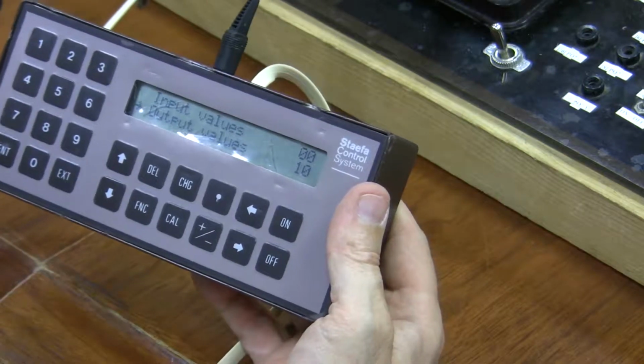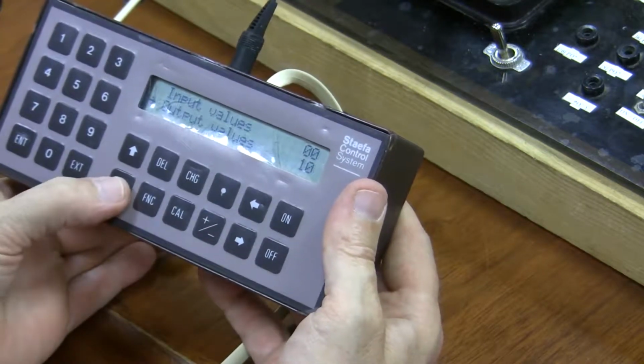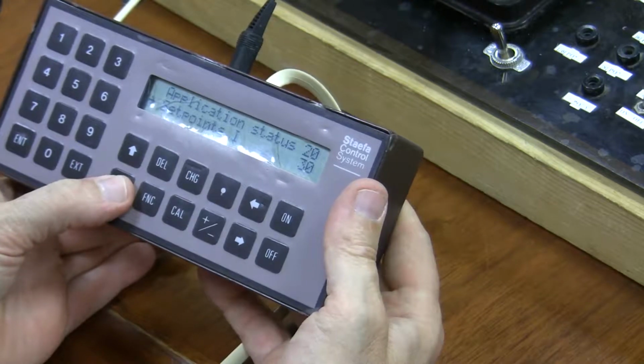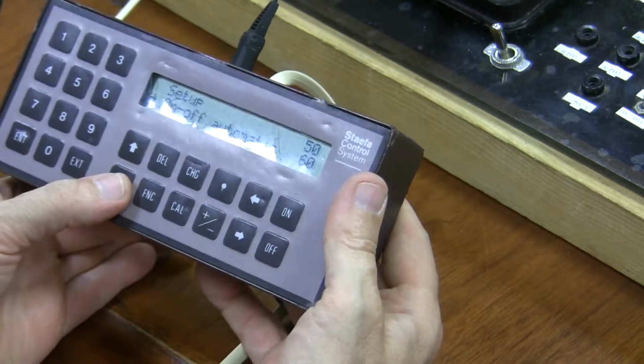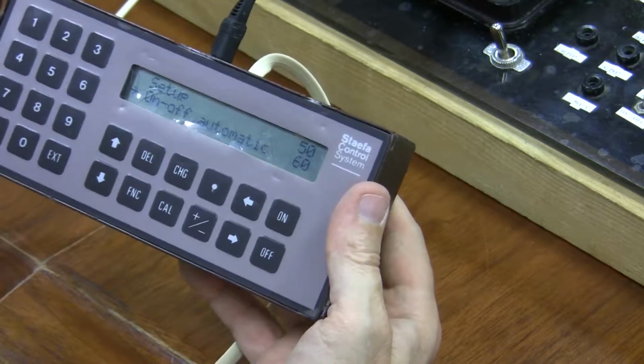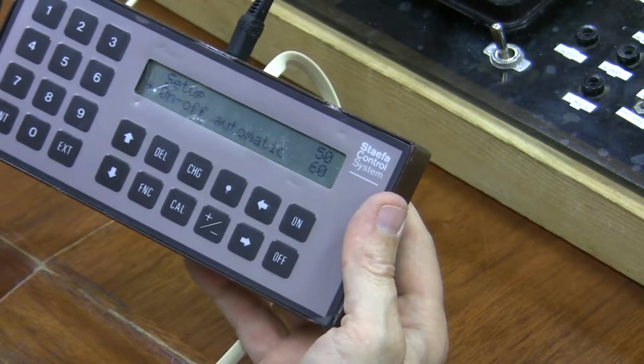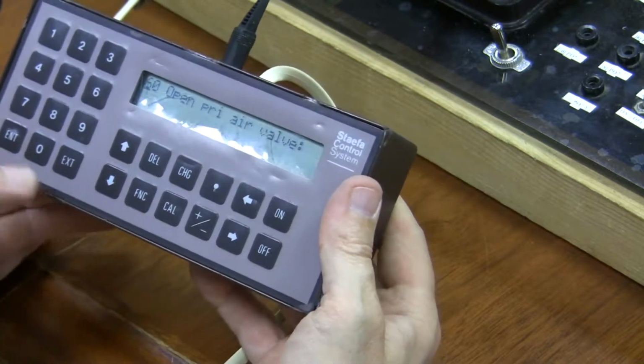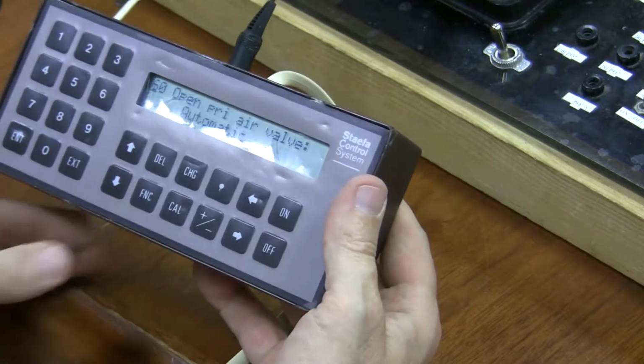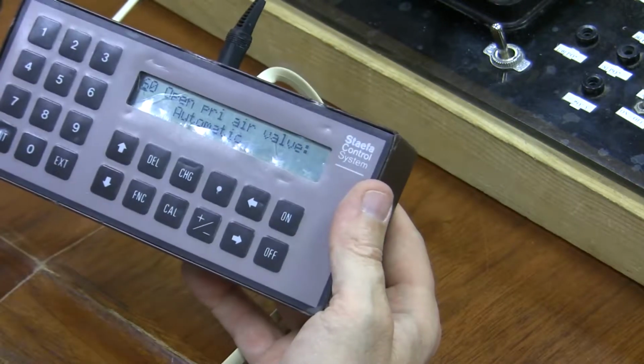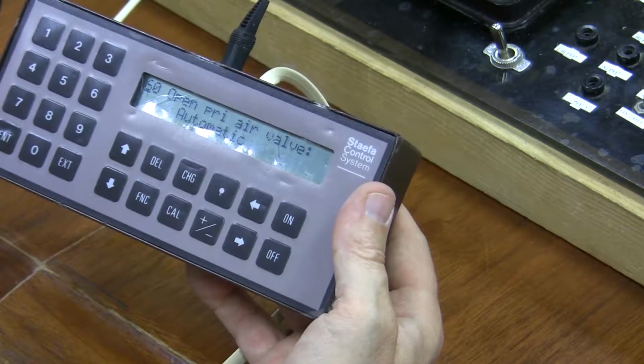If I want to actually control it, I've got to keep scrolling in the tens until I get to this parameter called on-off automatic. Now I could hit enter on this, and notice that's parameter number 60, and it says you want to open the primary air valve, and right now it's set to automatic.